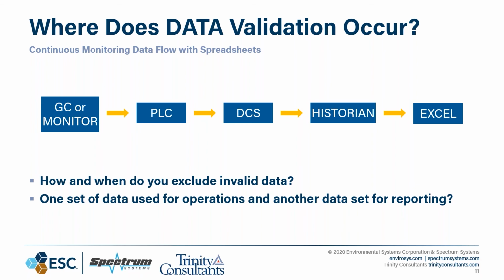So as you go into maintenance, you can optimize, and this is a helpful tip if your site is currently not doing this. Maintenance mode only requires 2 quadrants in an hour, so you can optimize 2 successive hours. You can throw your CEMS into maintenance mode on the 16th minute of that first hour, and then move all the way to the 44th minute of the second hour, and give yourself almost an hour and a half worth of maintenance with 2 valid hours. With the validated points, because you had the first quadrant, which is the 15 minutes, and then you operated that 1 point, that first minute of the 16th minute in the second quadrant, that gives you a valid hour. If anybody has any questions on how to do that, or if you don't think you're doing that, send us a question in the question pane, or you can email us and we can help you with this.